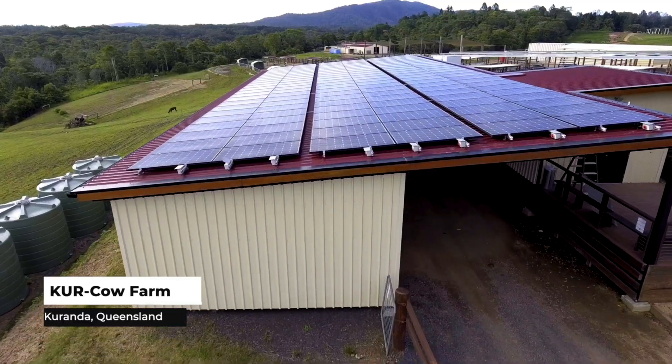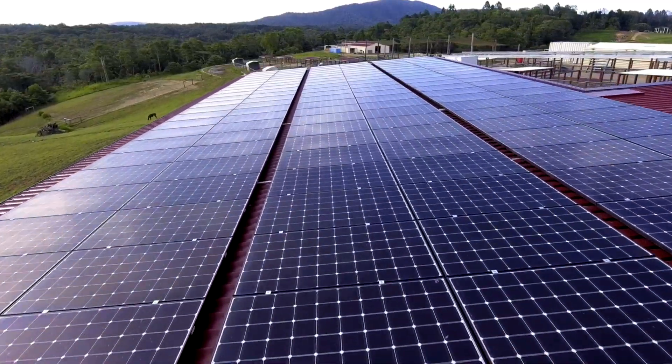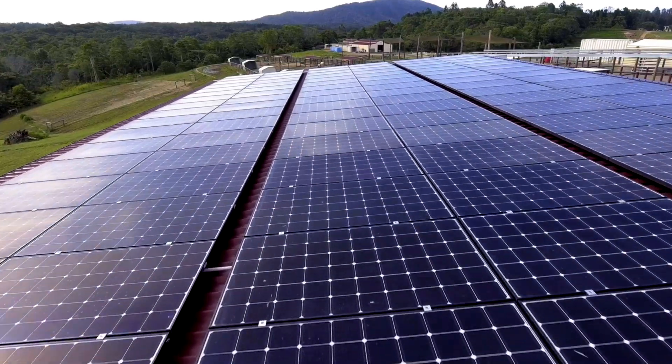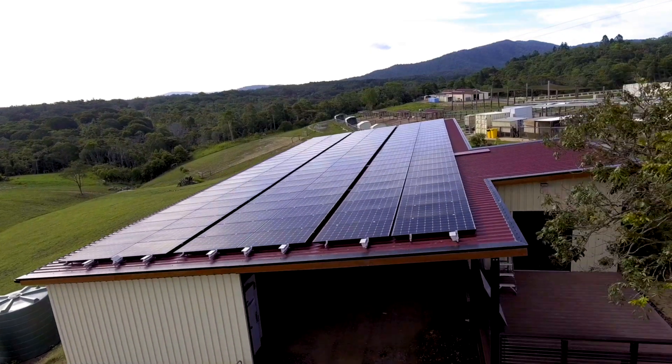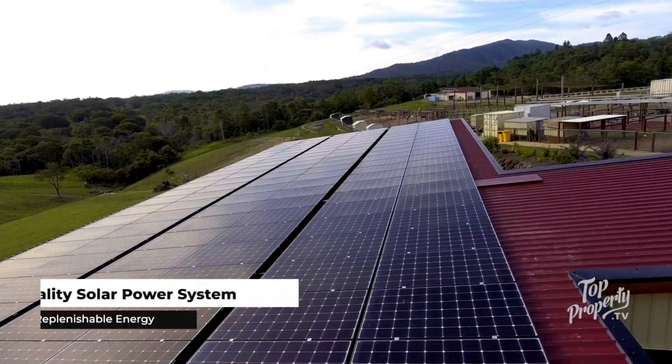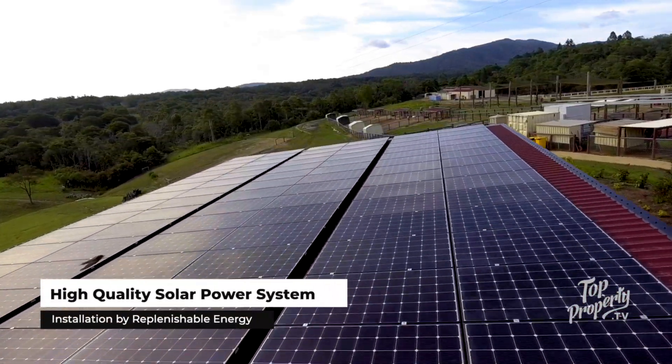KUR-Cow, being very conscious of an ecotourism-based industry, had a quality of supply power problem. They only had one weak two-phase supply coming in, and we had to literally double the amount of amps coming in. We did that with a combination of panels, hybrid inverters, and a series of batteries, just to cover the immediate load.